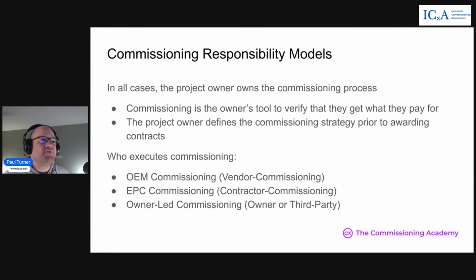So there are three primary commissioning responsibility models that exist. The first is OEM does the commissioning - this is if there's a vendor or manufacturer that's building the equipment. It's often best that they are the ones doing the commissioning because it's their equipment, and they're most familiar with it, and they can perform the detailed testing on their equipment. This can vary based on the size of the project.